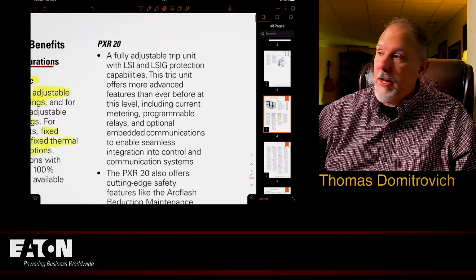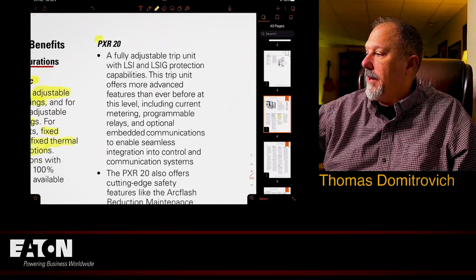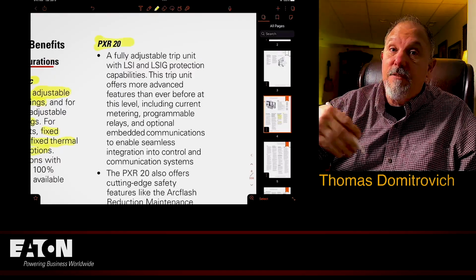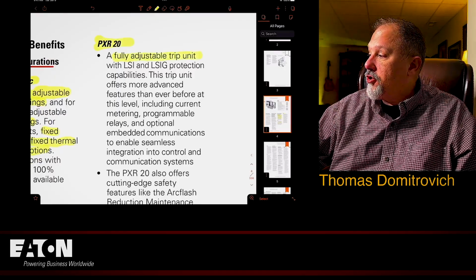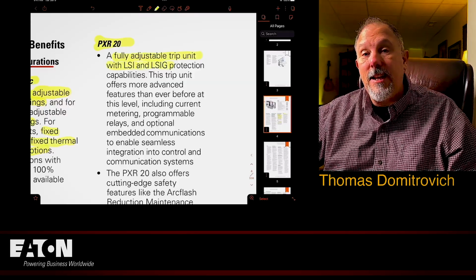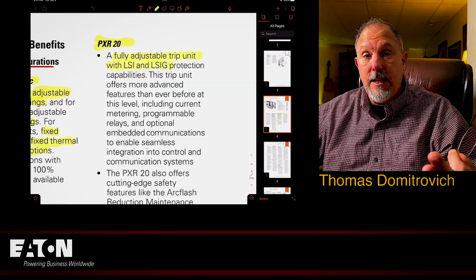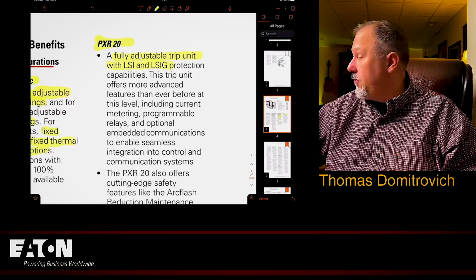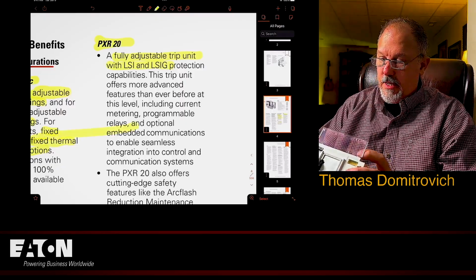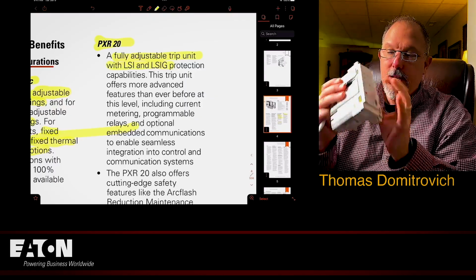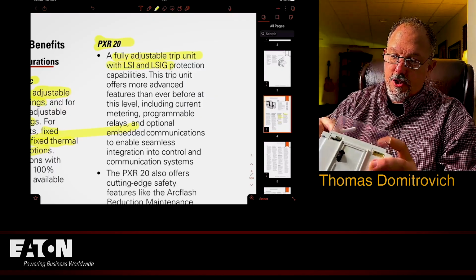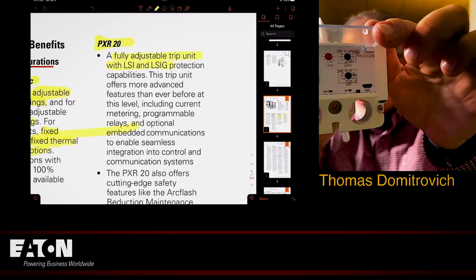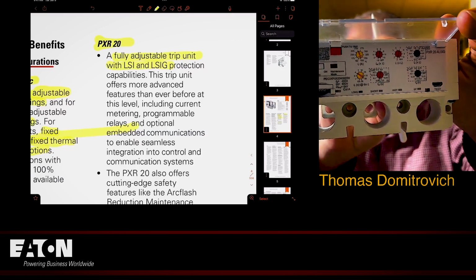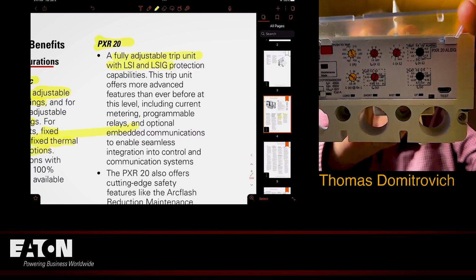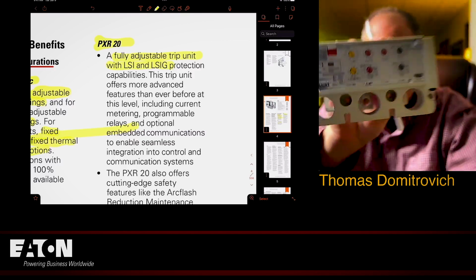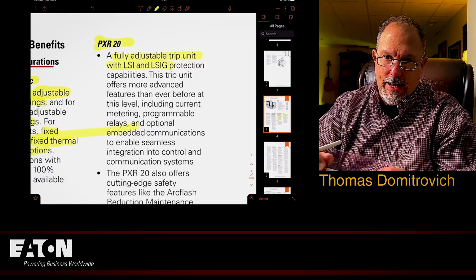So that's your PXR10, and then when you go to the PXR20, you're moving up in functionality. It's a fully adjustable trip unit with LSI and LSIG. So LSI, long time, short time, instantaneous. When you add the G, that is ground fault. This just happens to be a PXR20, and it has ground fault on it. There's your trip unit. This is a PXR20. Those are all the settings. And this is actually an LSIG.